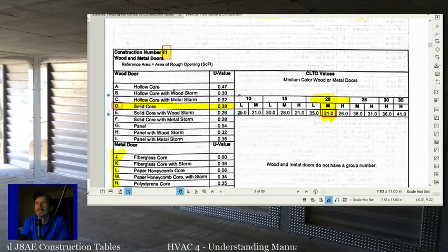But generally, colors are neutral enough, except for roofs, which they take dark into account, that you'll be okay doing a shortened load. So anyway, all the caveats aside, now we know that the effective temperature difference for our door is 31. So we will put that 31 and then multiply it times the U value for the door, which is 0.39.